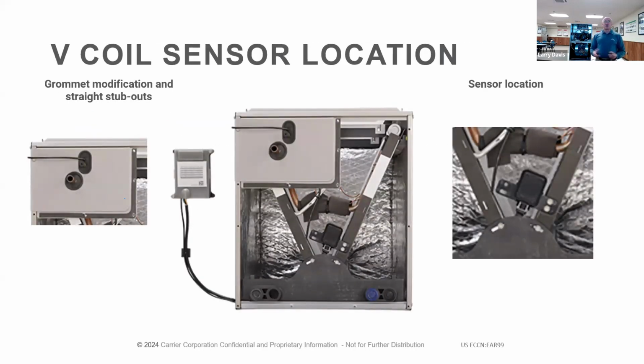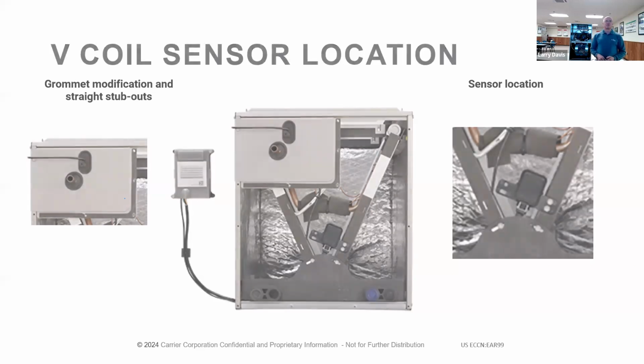For the evaporator coils or the V coils or A coils, the sensor, that dissipation board is going to be externally mounted. The sensor runs through a cable through a grommet. You see the straight out stubs there again for the coils. Runs through a sealed grommet and the sensor is located. If the coil is a multi-poise and you're in horizontal, there'll be instructions on where to relocate that sensor.